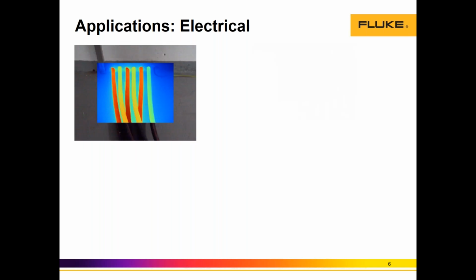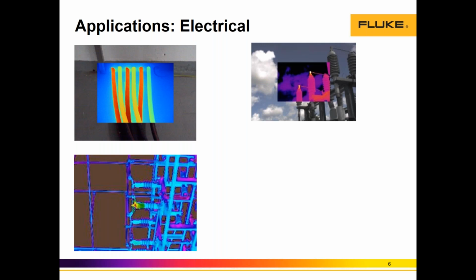Let's talk about the applications. One of the biggest applications for TI is the electrical sector or electrical systems. Most, if not all, faults in electrical systems usually result from a change in flow of electricity, or an overload in specific phases. The common denominator is that in the area where that problem is happening, whether we have an overload phase or a disbalance problem, we'll see an increase of heat or temperature. And here's where the camera always plays.